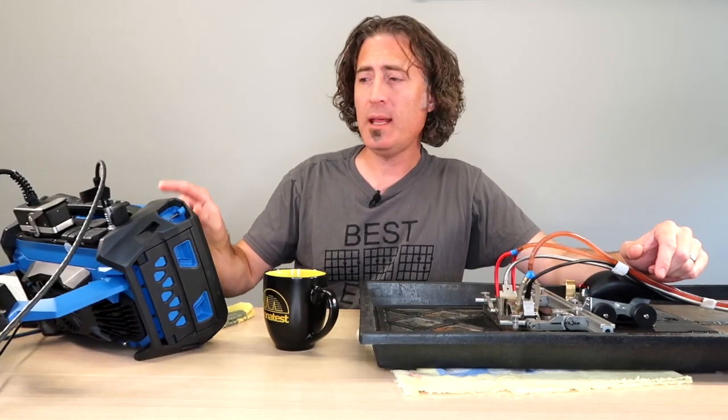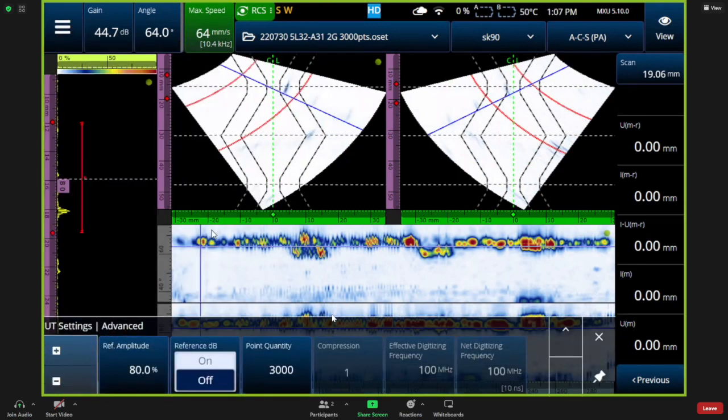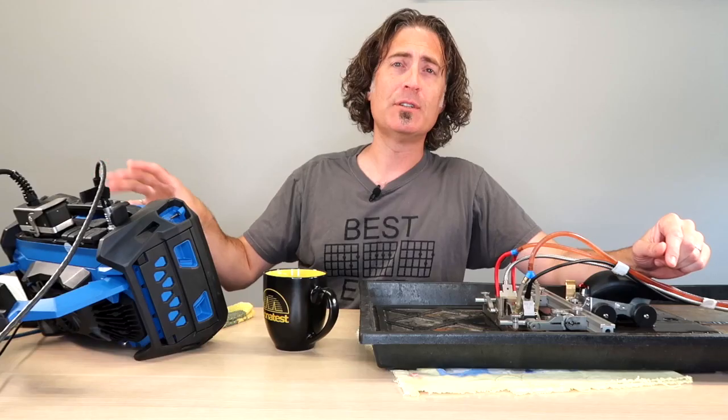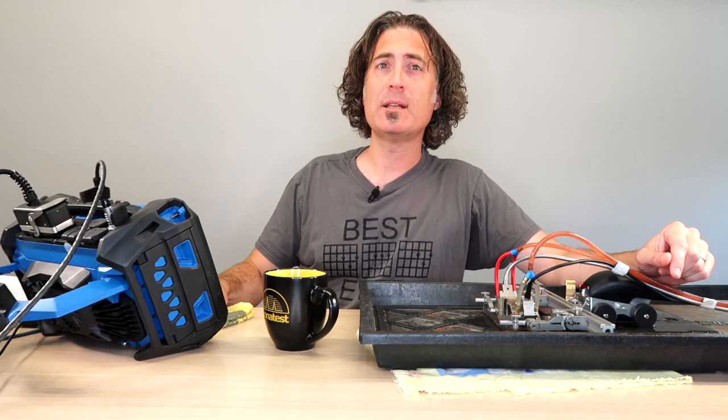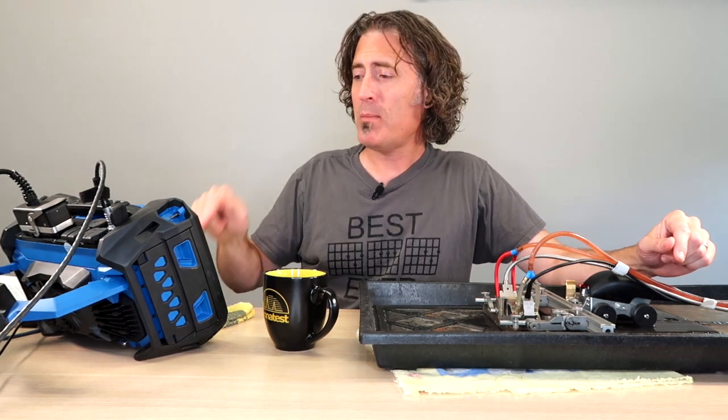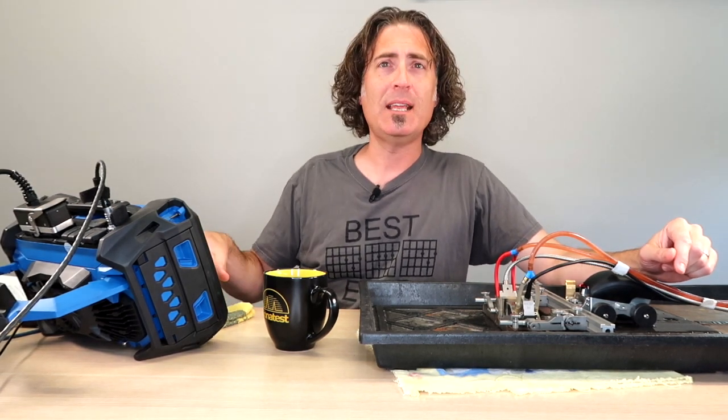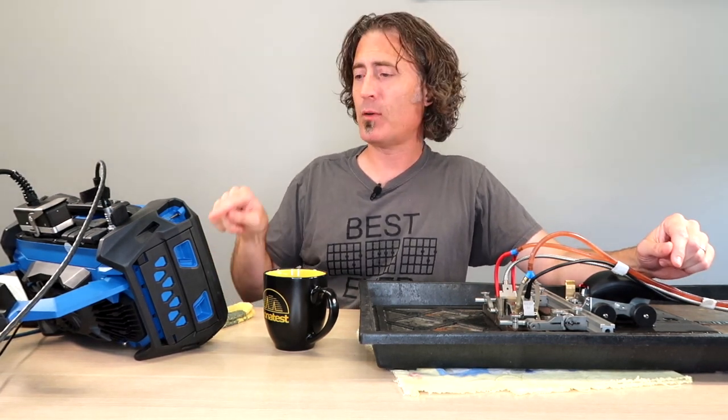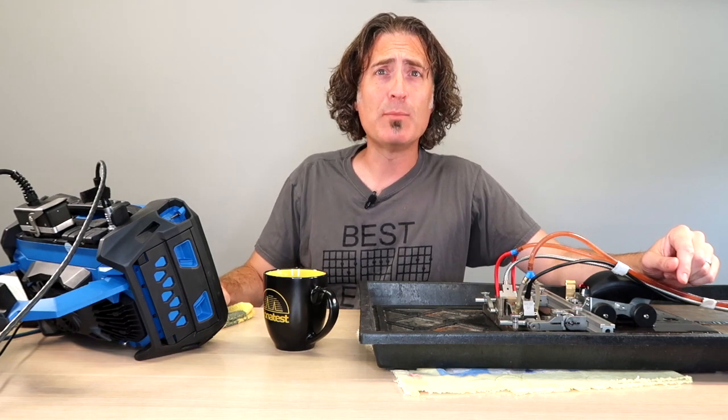You'll find Points Quantity in the UT Settings Advanced menu. You see Points Quantity is available for us to change. Everything else is grayed out. That's the way it is up to version 5.10 on this operating system. In the future, we might be able to change the other things independently, but for right now, the only thing we can monkey with is Points Quantity.